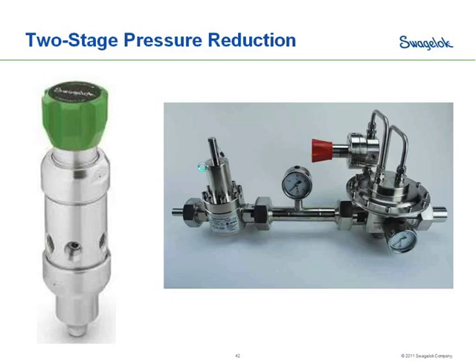As pressure decreases on our inlet side, we see the inverse effect on the outlet side of our first regulator. So if we stay with the example we looked at a few minutes ago where we drop from 3,600 psi down to 1,600 psi on our inlet pressure, and we're trying to control a 50 psi outlet pressure, now the outlet pressure of that first stage is going to go from 50 to 70. That second regulator, instead of seeing a decrease on inlet pressure, sees an increase on inlet pressure. So the pressure to the second regulator goes from 50 to 70. So that second regulator will see a decrease in outlet pressure. That's 1% of that change. So you have that 20 psi change, so you'll see 1% of that on the outlet side.